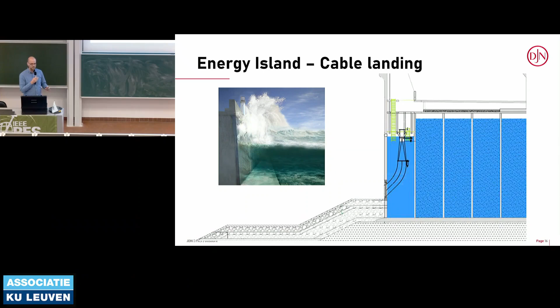Whilst with a monopile or jacket, the wave comes in, opens, and closes again. Here you have a huge amount of energy impacting the cable, so you need to protect it. The cable needs to handle all these forces, so that's also part of the design for a submarine cable.